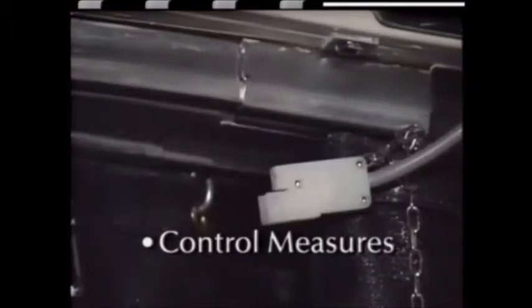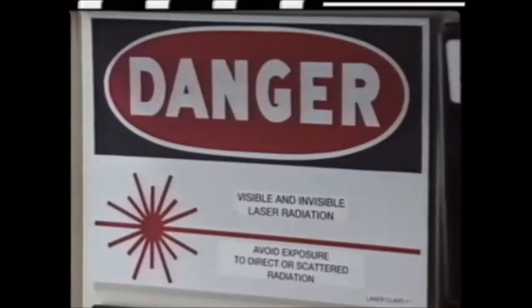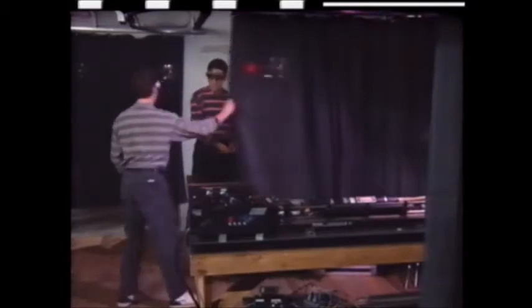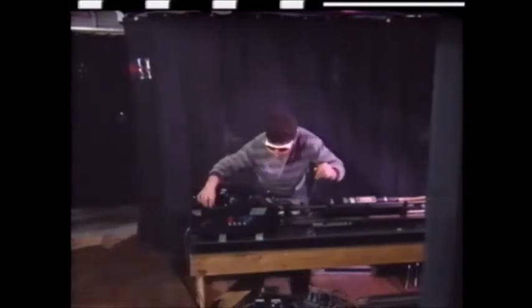To protect people entering the lab, place interlocks on the door to the lab or place curtains or coverings over the doorway while the laser is in operation. Post a danger sign outside the door to the lab. To decrease the risk of exposure to people inside the lab, use temporary barriers. Beam stops that absorb the beam and that are fire retardant prevent beams from leaving the benchtop.